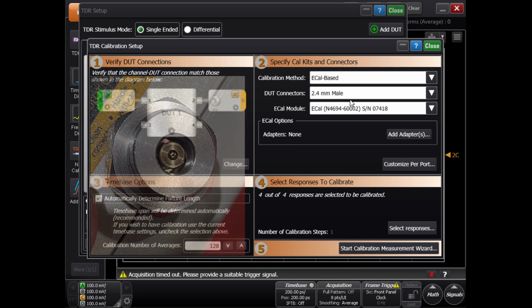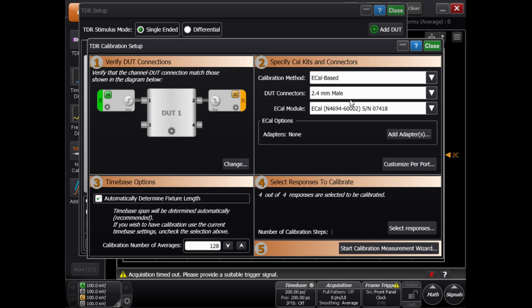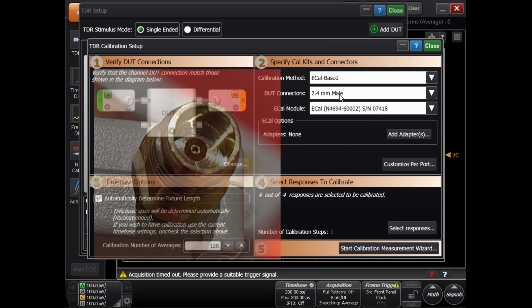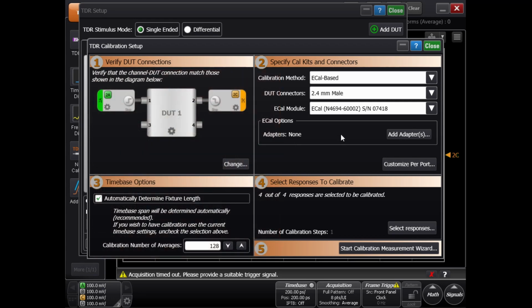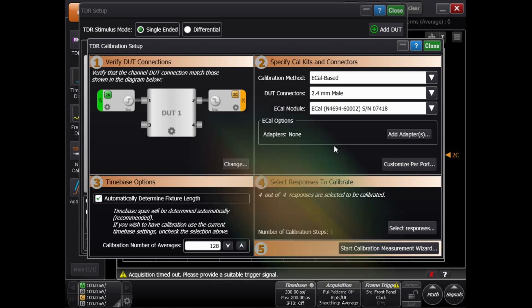The second thing is whatever adapters I need to stick on my TDR head, I will put them on. They aren't accounted for in here because the reference plane is at the end of the adapter on the end of the TDR. In my case, I have a female connector, 2.4 millimeter, on my N1055 head. That means I can directly first connect to the DUT, and secondly, for calibration, I can connect it direct to the Ecal. There's really nothing to do. No adapters are needed.